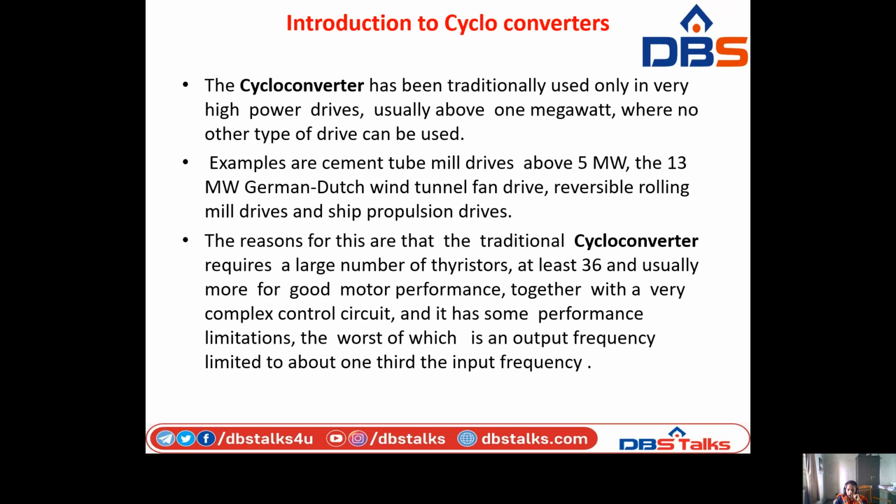The reason is that traditionally the cycloconverter requires a large number of thyristors, at least 36, and usually more for good motor performance, together with a very complex control circuit, and it has some performance limitations, the worst of which is that the output frequency is limited to about one third of the input frequency.